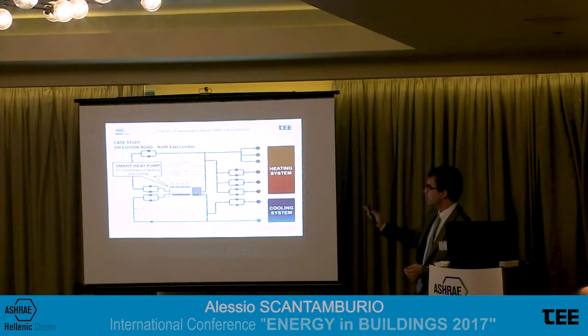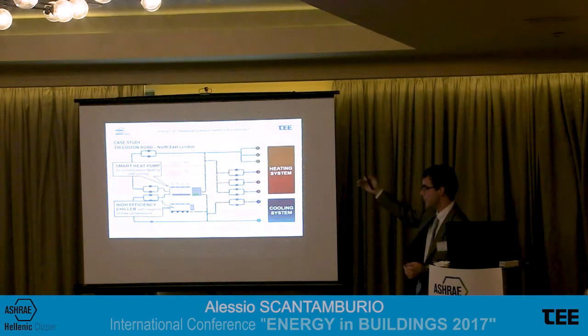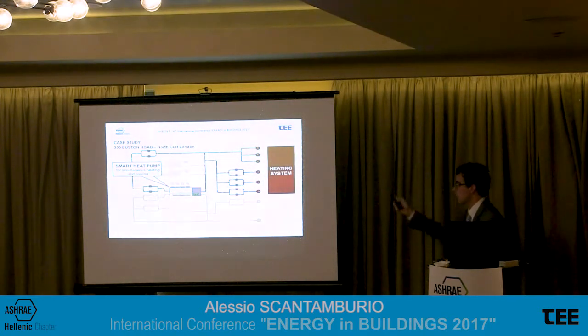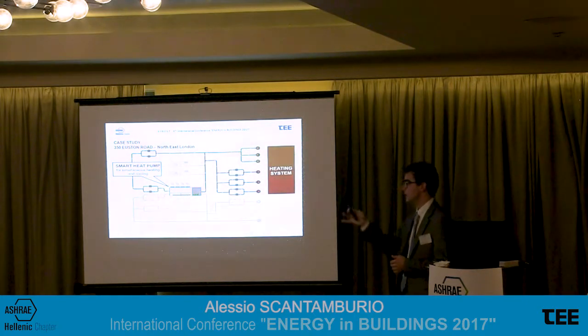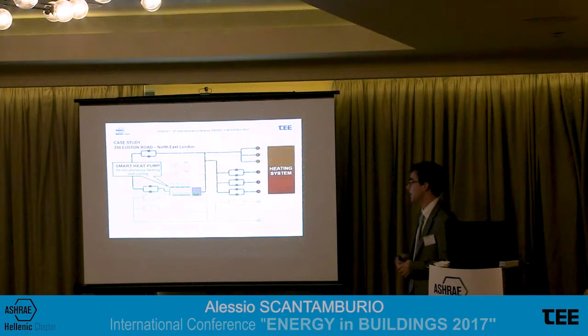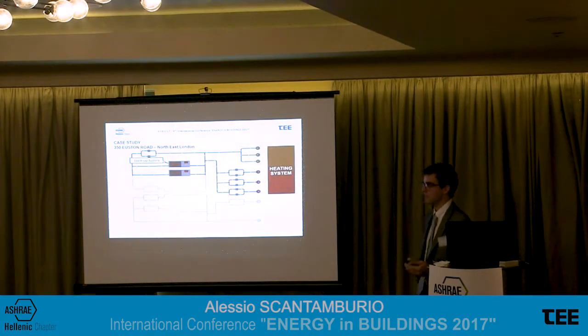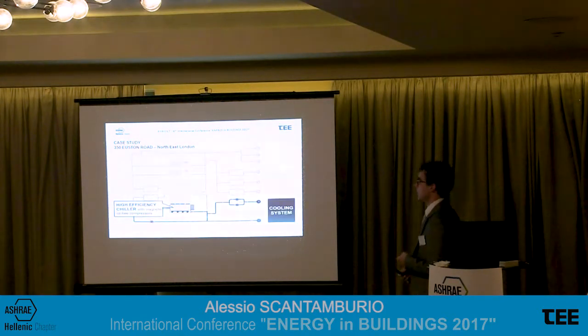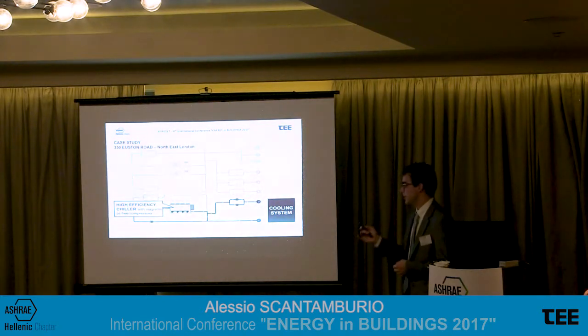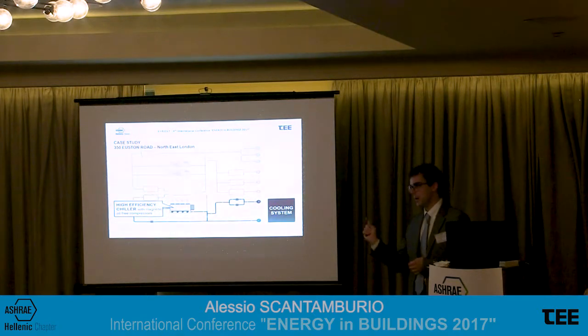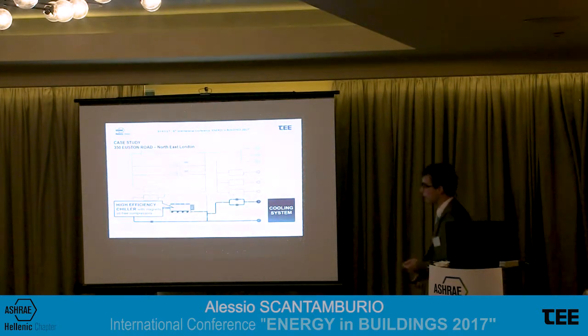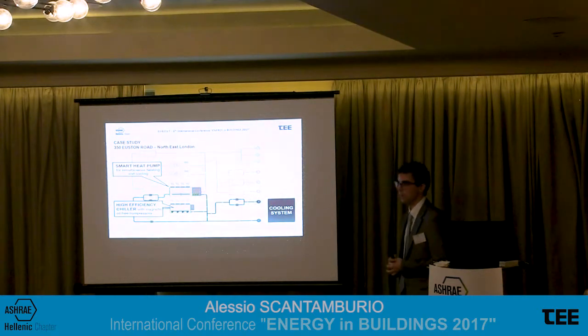Okay, so if the building is requiring at the same time hot water and cold water, of course, the system uses a 4-pipe unit. And in case we have higher cooling capacity, then the system kicks in the chiller. Of course, when the building requires only hot water, the plant is running only the smart heat pump, and the backup boilers in case they are needed, for example, for very low external air temperature. And this is the case where the plant is requiring only cooling capacity in the summer months, where we have only cooling load. We run the chiller and then the 4-pipe unit in cooling mode.